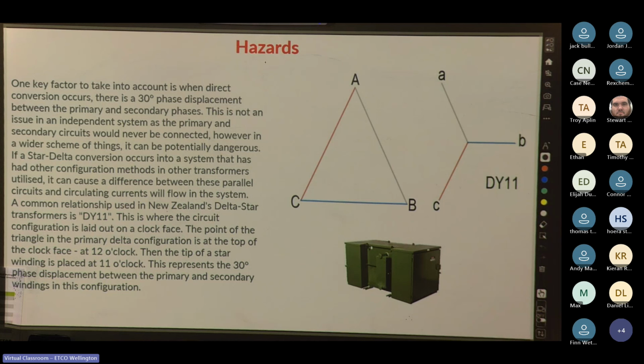Correct me if I'm wrong, line guys. A common relationship used in New Zealand's delta star transformers is DY11. This is where the circuit configuration is laid out on a clock face. The point of the triangle in the primary delta will be at 12. The tip of the star winding is placed at 11. This represents the 30 degree phase displacement between primary and secondary windings in this configuration. So, some more key facts.